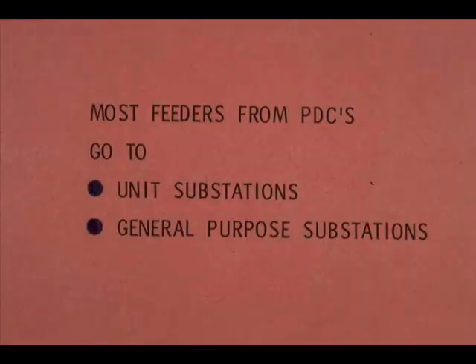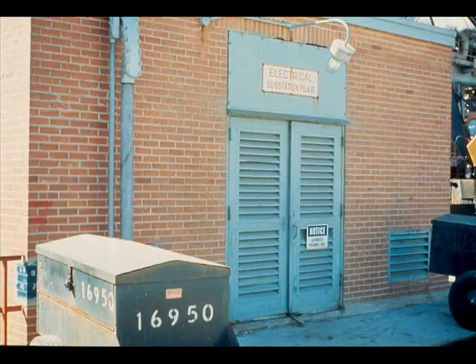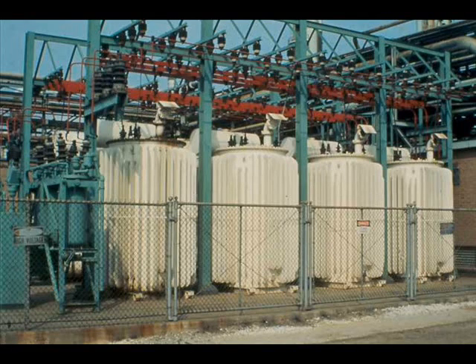Most feeders from PDCs go to substations, which one large plant classifies as unit substations or general purpose substations. A unit substation serves a single process unit; for example, PSLA-10 substation serves number 10 pipe still. A general purpose substation is not limited to serving a single unit — one such substation is S-10, named because it is on Avenue S and 10th Street. At substations, transformers step down 13,800 volt current to 2,400 volts, 480 volts, 240 volts, 120 volts, or other required voltages.